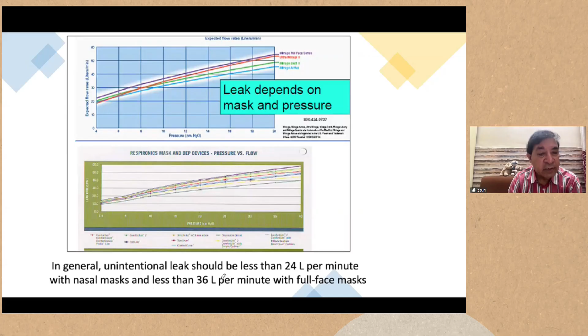So you must know the level of normal leak or the intentional leak for a given pressure. And that's what you see. Normally, it is usually less than 24 liters for all pressures. It is less than 24 liters for a nasal mask and less than 36 liters for an oronasal mask. So this is one concept you have to understand.